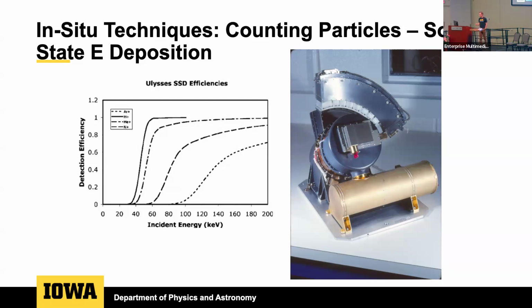So this is an older instrument here, but a good one. This was flown on Ulysses, and what this is showing you is the detection efficiency as a function of energy for different masses, different species of ions. The solid line here is the protons. Protons lose less of their energy to things other than creating electron hole pairs, and so your efficiency for protons is pretty good, close to 100% once you get above a threshold energy. But as you go to higher and higher mass species, by the time you get up to argon, you can see you have to have a whopping big energy before you get anything out as far as a charge pulse, and the efficiency is a lot less.